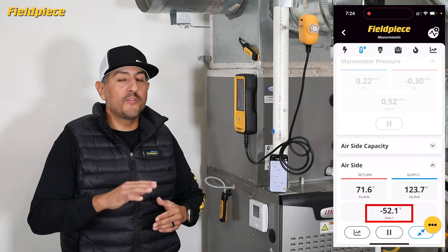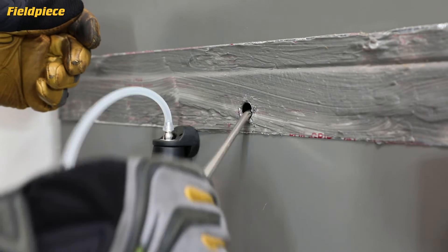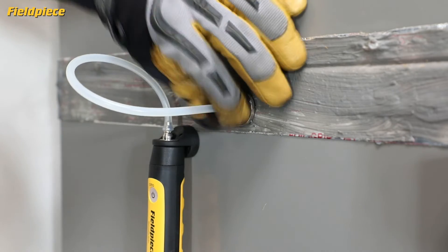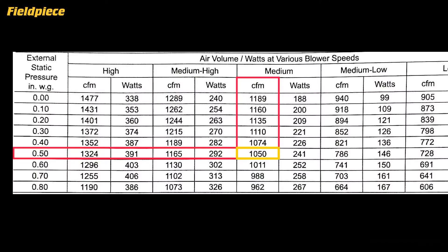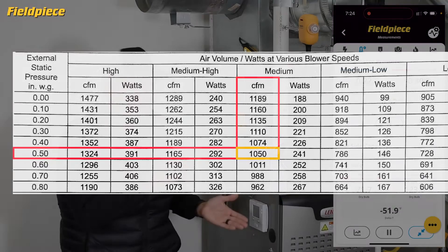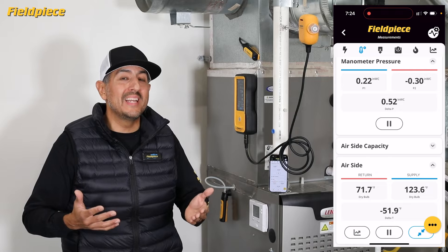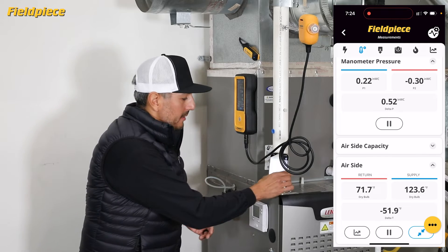On the airflow side, you can use a couple of JobLink wireless manometers to measure the total external static pressure, and look up the manufacturer's blower data tables. Knowing that this fan is set to medium right now, I see that my estimated CFM is 1050.